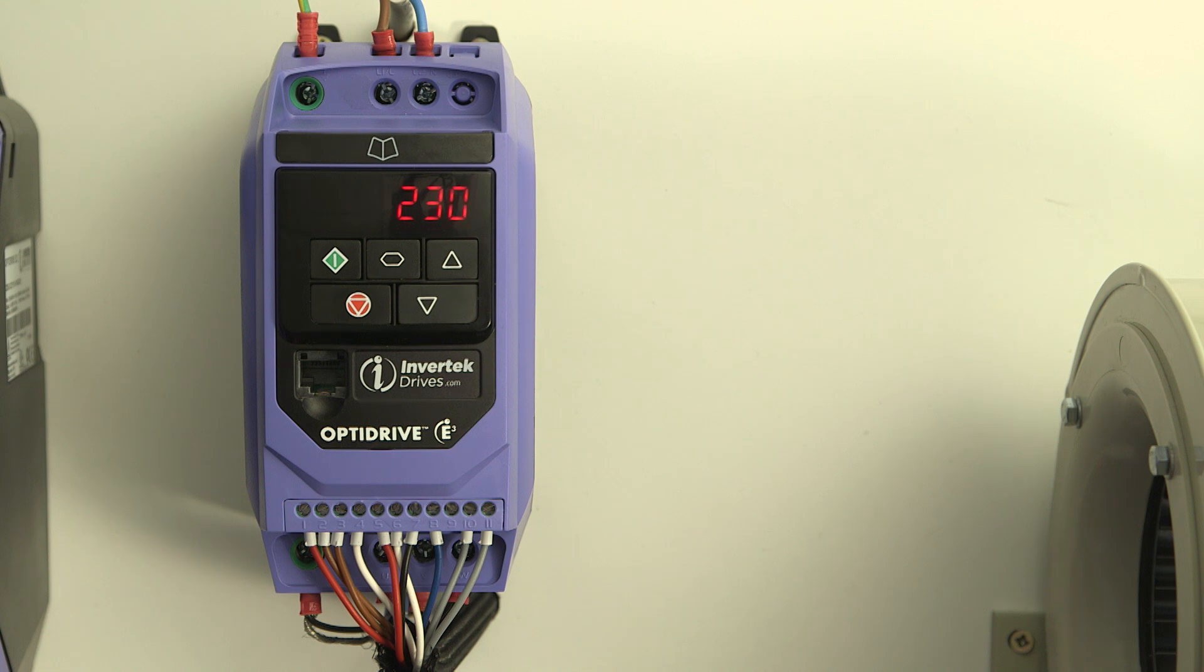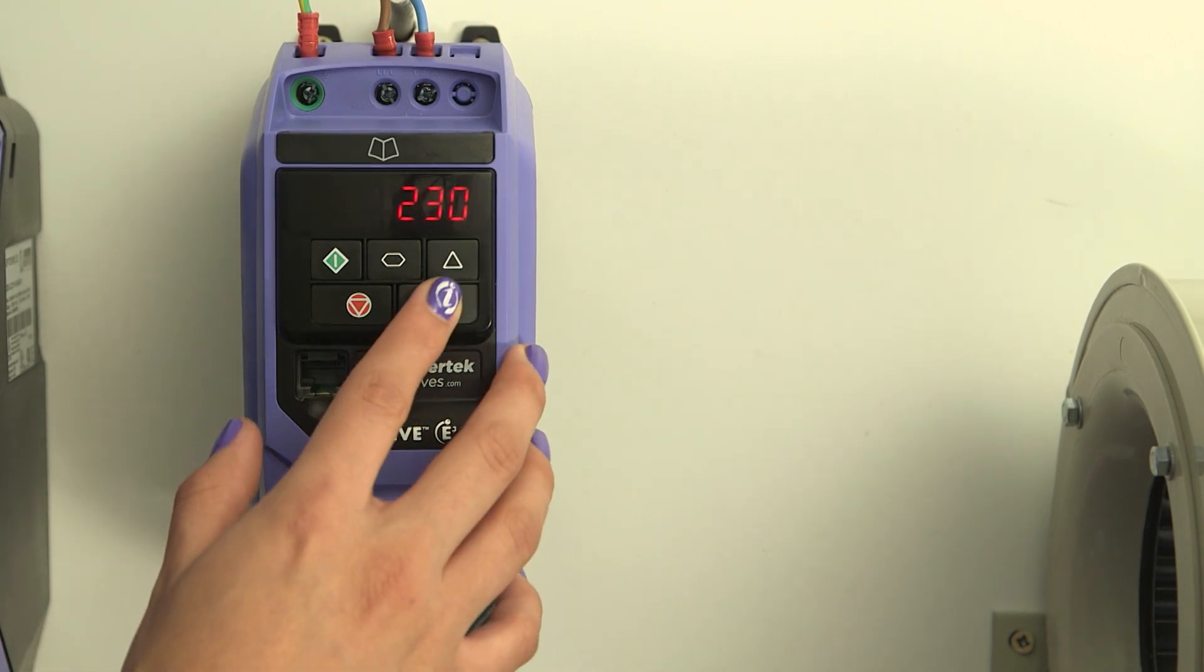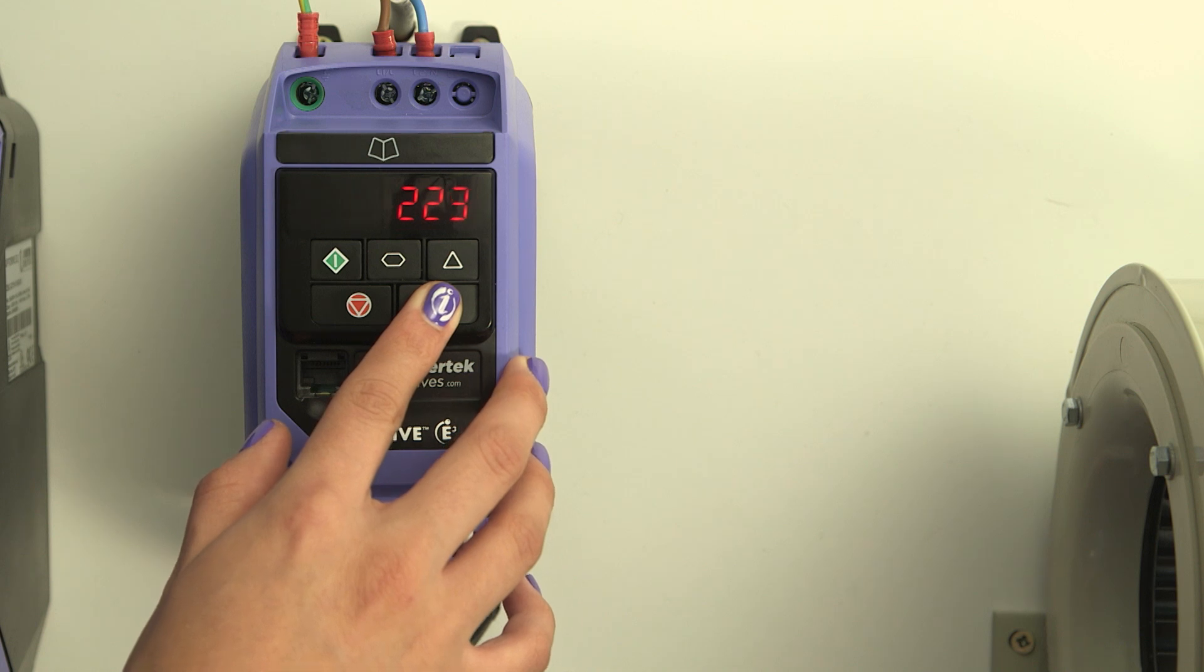This can be a bit tricky with these motors as we need the nominal voltage or back EMF that the motor produces at rated speed. This may be shown as UN on the rating plate or datasheet. The motor we have is 160 volts, so I'll put that in.